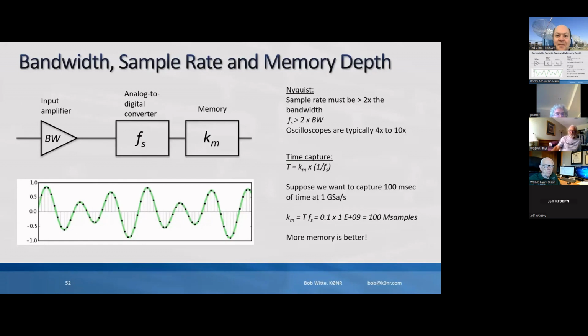The thing that's still a big issue is time capture, because ideally I'd like to capture at my highest sample rate all the time, no matter where my settings are. So here's the equation for that. The time captured is my memory depth, K sub M, times 1 over the sample rate, right? If I take the reciprocal of the sample rate, that gives me the sample time, the time between each sample. So that's my equation that relates time captured, memory depth, and sample rate.